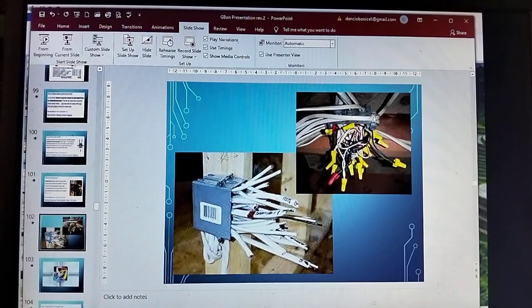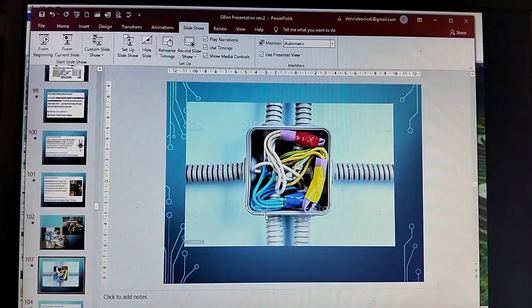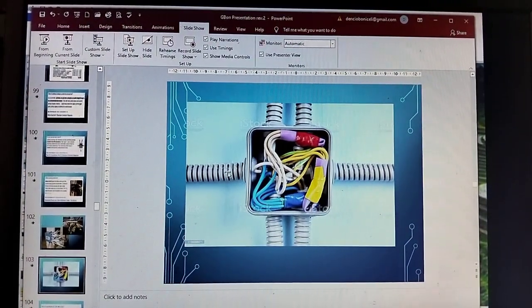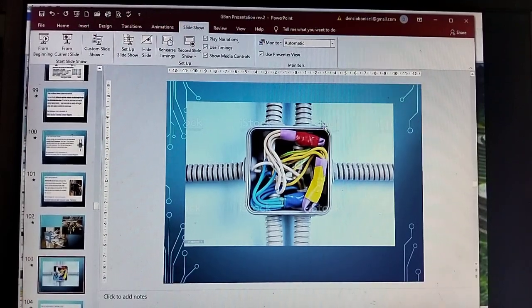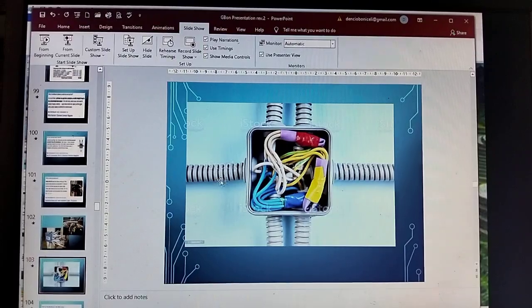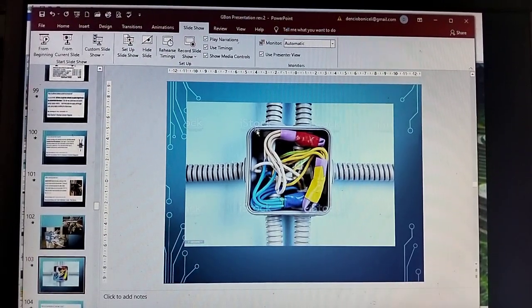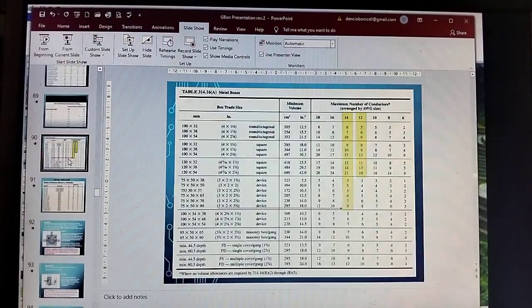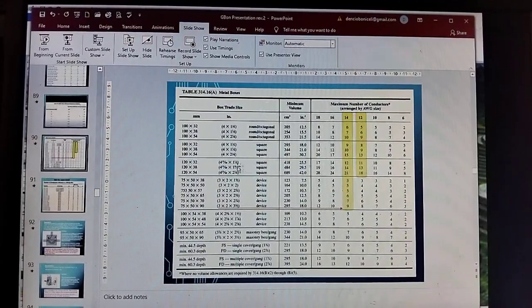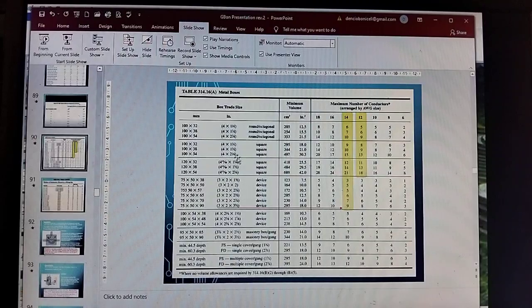Here, you think this is allowed? No, this one also is overfilled, with a tendency for fire. Even this one, let's say you have a junction box and you have 6 conduits. Each conduit contains 4 individual conductors, so 4 times 6, 24. Whereas on the standard, let's say you use a square box, 4x4 by 2 and 1/8, you only have 13 if you are going to use size 12 wire.